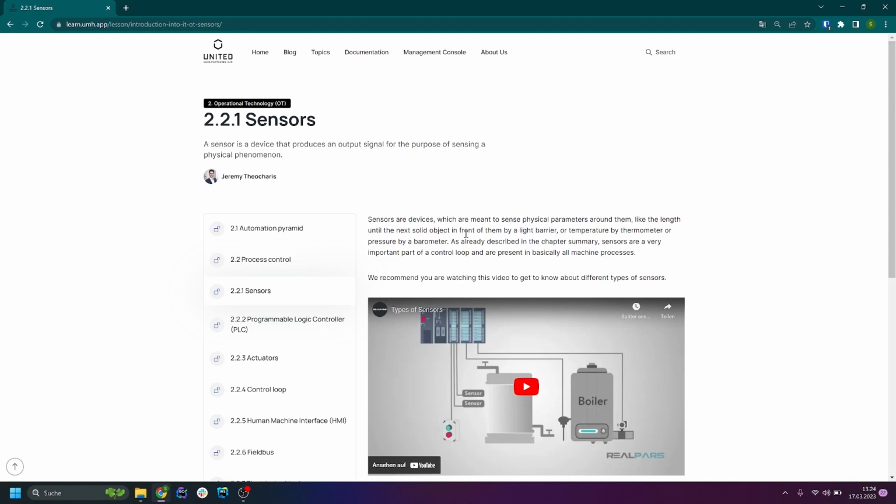Yeah, so in IO-Link, all of these components that I just described, like converting a resistance into 0 to 10 volt and then having an analog-to-digital converter, they're all inside of these sensors. And then additionally, you have some advanced logic on it. You take an IO-Link sensor, you connect it to an IO-Link gateway. We're using a lot of the IFM ones out there, the IFM IO-Link masters, we even have sensor connect to automatically read it out.